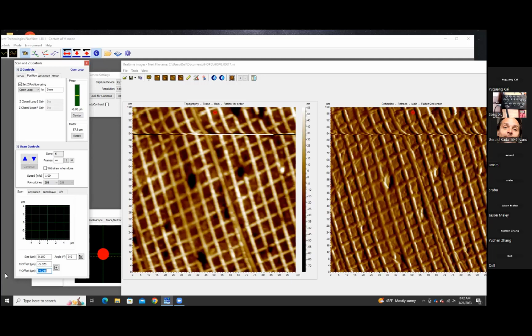So all we're looking for here is that your power supplies move to the extremes as the software tells them to. So you go ahead and center it back and disengage your high voltage. And that's your basic high voltage test. That tells us that the system is working properly. If there was a problem with one of those high voltages, the polarity may not change, the value may not change. We're really just looking for change in the direction that we're expecting. So your power supplies are good to go.